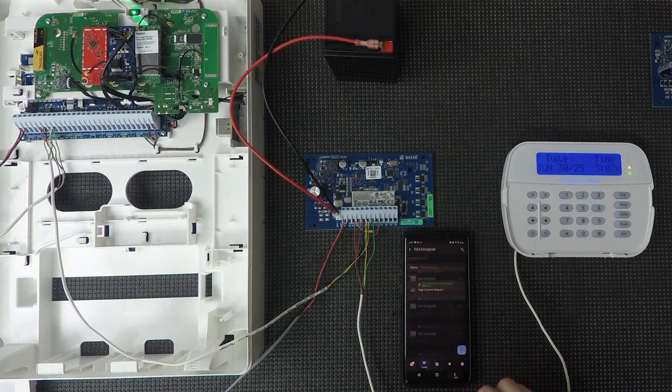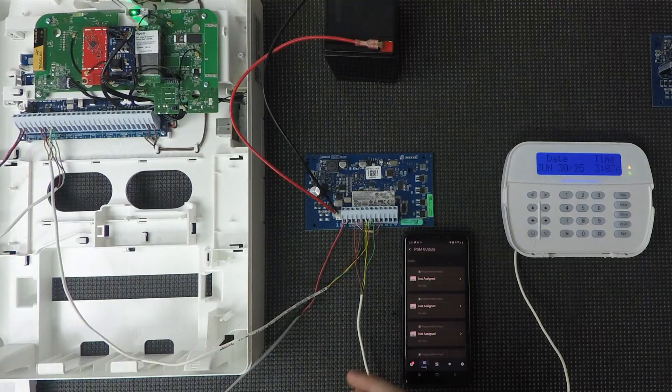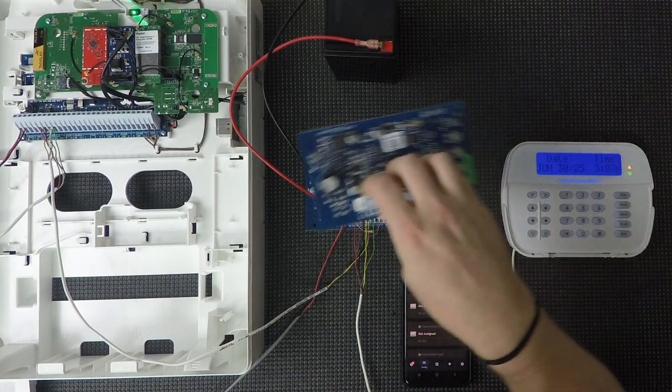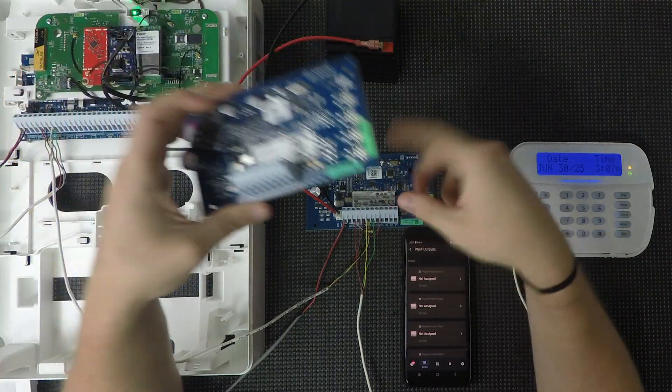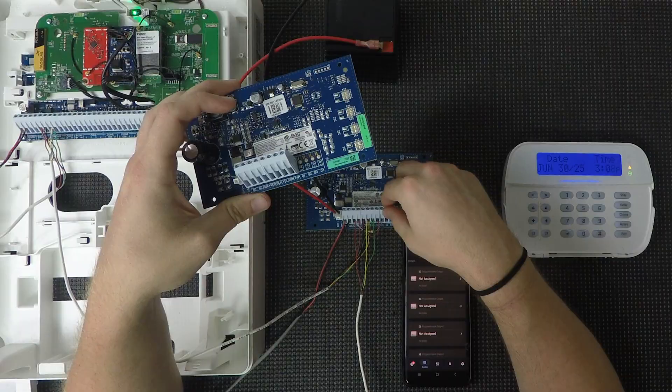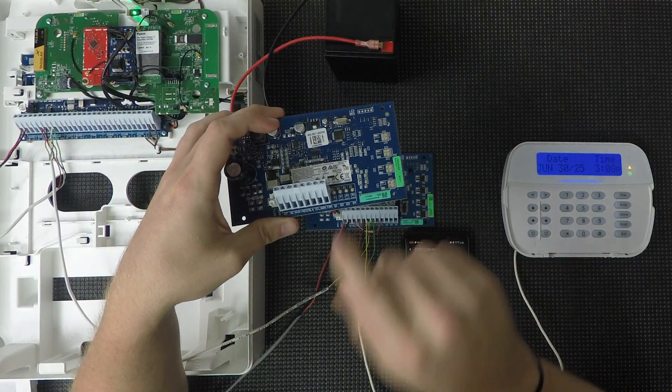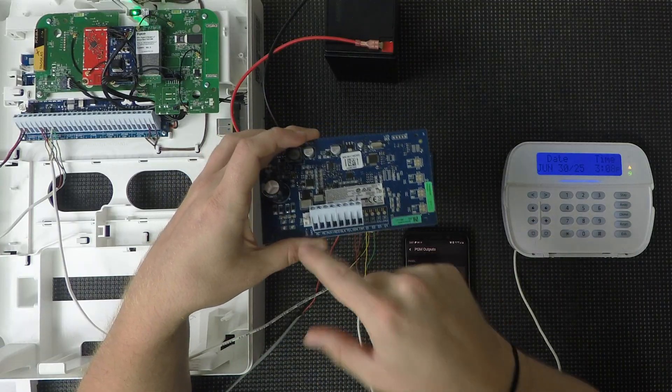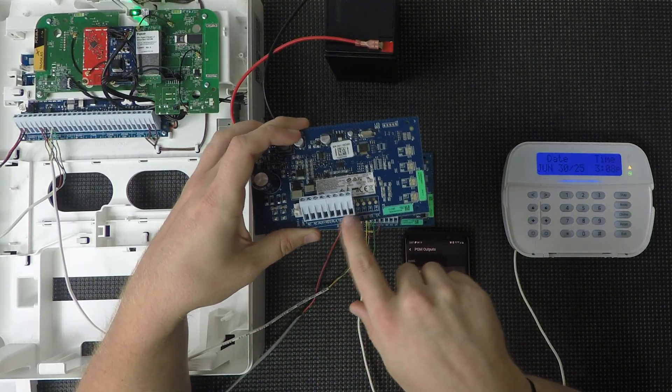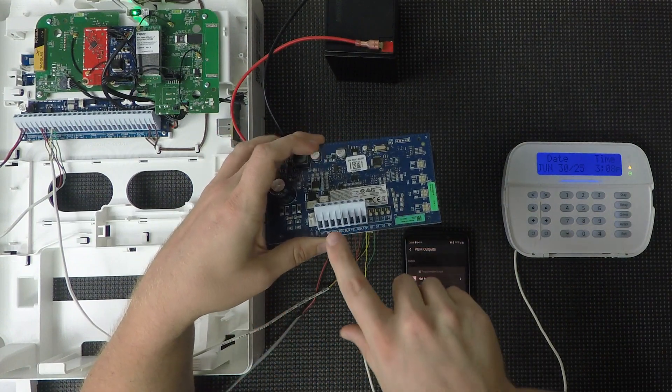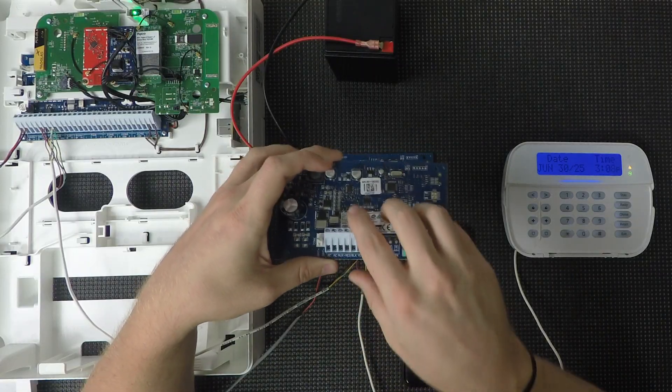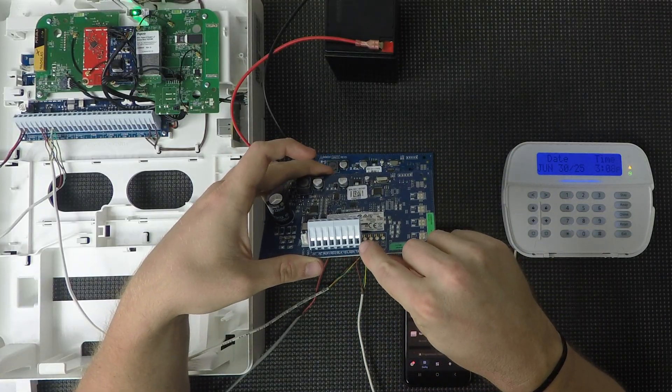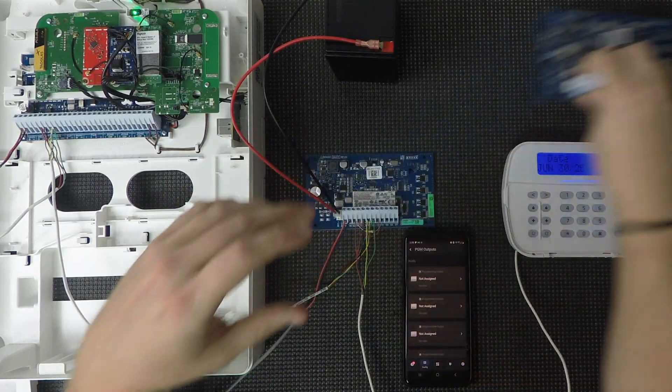So that is basically the ins and outs of using a power supply module on this system. Now, just real quick, if we were going to use the 2300 instead of the 2204, everything else except for what I mentioned regarding the output supplies. So same thing, you'll need the two AC wires connected to a transformer. You'll need a battery connected. Your Corbus will pull power from the main system. And then your aux plus here is your output for all power on this device. It does also have the tamper terminal right there. So you'll need to either use a switch or use a jumper like I did.